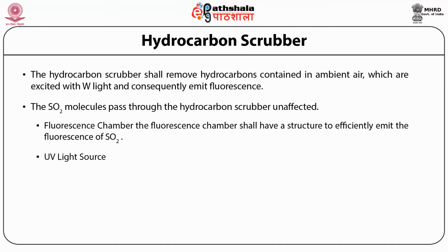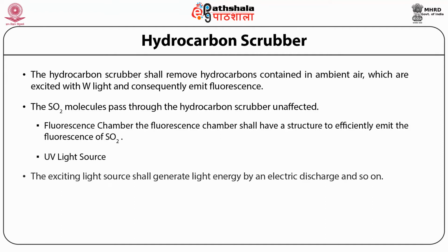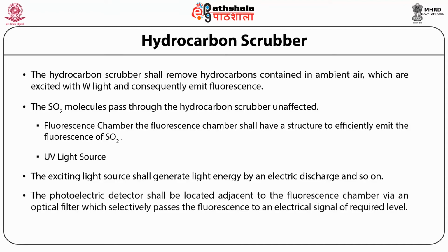Then the UV light source, the exciting light source, shall generate light energy by an electric discharge and so on. Then the photoelectric detector shall be located adjacent to the fluorescence chamber via an optical filter which selectively passes the fluorescence to an electrical signal of required level.